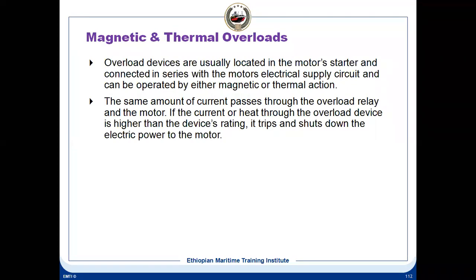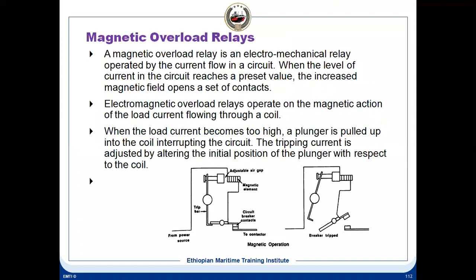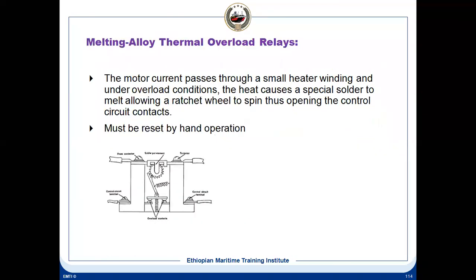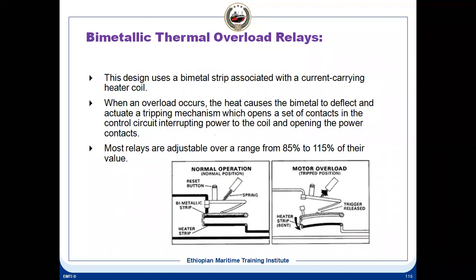Overload devices are located in the motor starter and connected in series with the motor electrical supply circuit, and can be operated either by magnetic or thermal action. So the same amount of current passes through the overload relay and the motor. If the current, or the heat through the overload device, is higher than the device setting, it trips and shuts off the electric power to the motor. So this is a magnetic type and the other is a thermal type. This is a melting alloy type and this is a bimetallic type.